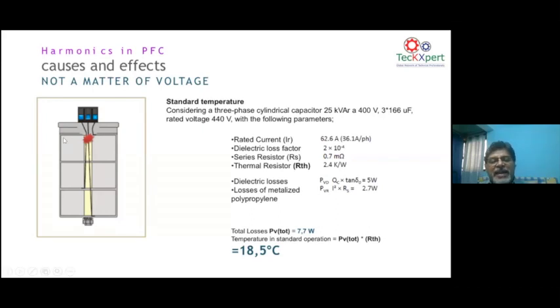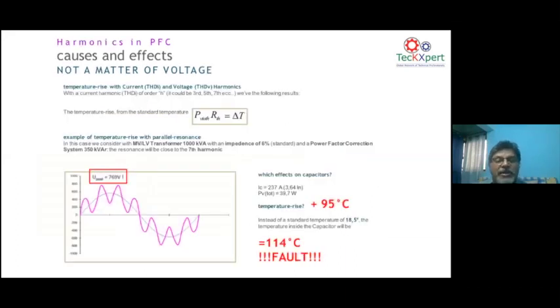So typically a standard capacitor has a certain amount of losses. And if you go and touch the case of the capacitor, you generally don't get any hot surface, because these resistances typically give around 0.5 watts or so of capacitor loss per kVAr. So you generally don't get the capacitor casing that hot in normal situations. But now imagine your harmonics. Now the harmonics are flowing, naturally the temperature goes up. Now here you can see a distorted voltage waveform.